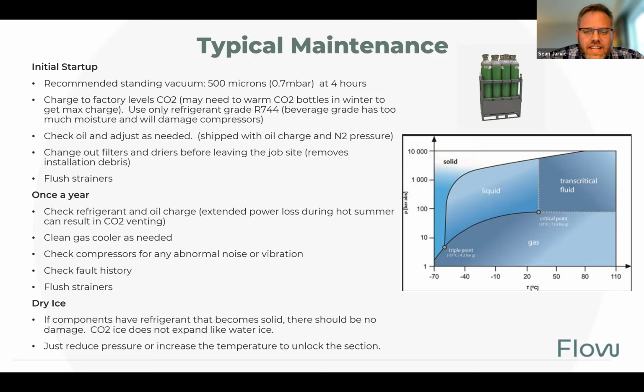There's another element related to the high pressure that CO2 can run. What's really unique is it doesn't make a jet of laser-cutting CO2 gas. Instead it makes a small crack and leaks, then rapidly expands and forms dry ice, which closes it off partway. You get a built-in leak detector, with a nice ball of clean white frost coming out of the system so you know exactly where your leak is, making it awesome for troubleshooting.